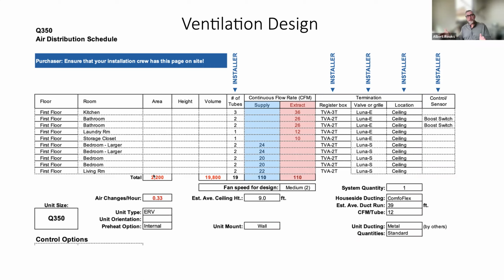And in the extreme edges of the climates, maybe you have to add humidification, or you have to add dehumidification because you're in an extreme climate rather than in the middle climate ranges. So if we take those conditions and we start increasing the flow rate, then the flow rate pushing the humidity out increases, but the occupants don't create more moisture. So we're actually going to slowly dehumidify the house.